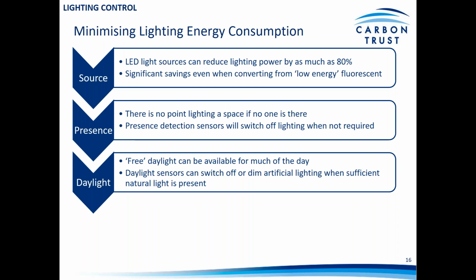So again, we've looked at this in the lighting webinar, but it's often the case that you can see significant savings by changing your light source. So going from conventional fluorescent or metal halide or indeed incandescent technology to LED will provide good savings. Typically 70–80% is possible in doing that.